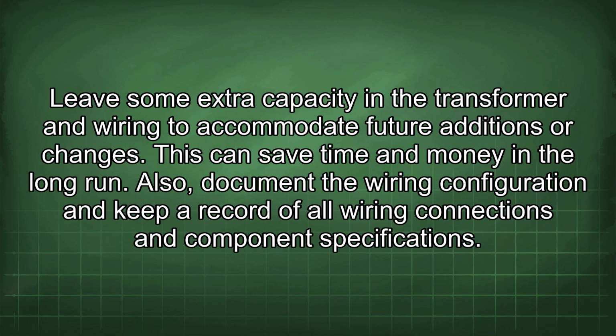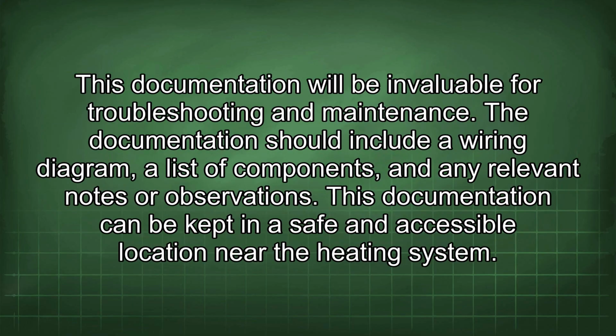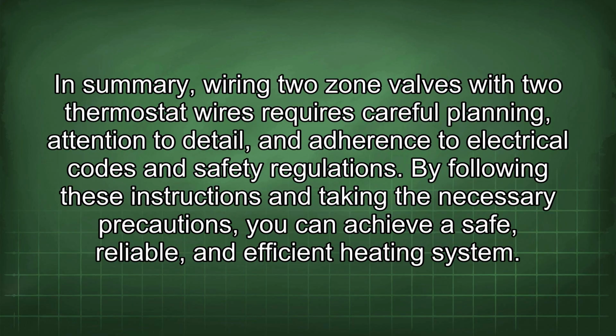Also, document the wiring configuration and keep a record of all wiring connections and component specifications. This documentation will be invaluable for troubleshooting and maintenance. The documentation should include a wiring diagram, a list of components, and any relevant notes or observations. This documentation can be kept in a safe and accessible location near the heating system. In summary, wiring two zone valves with two thermostat wires requires careful planning, attention to detail, and adherence to electrical code and safety regulations. By following these instructions and taking the necessary precautions, you can achieve a safe, reliable, and efficient heating system.